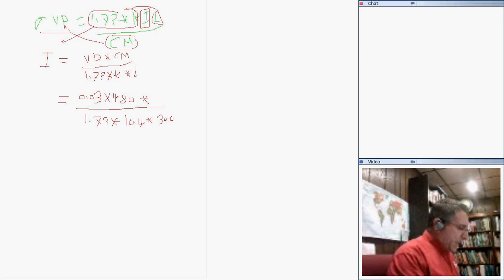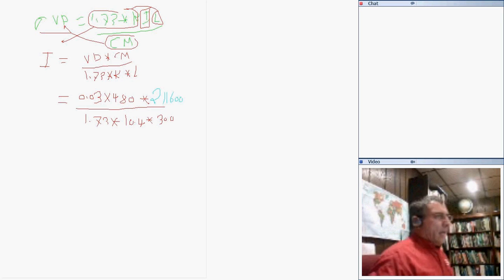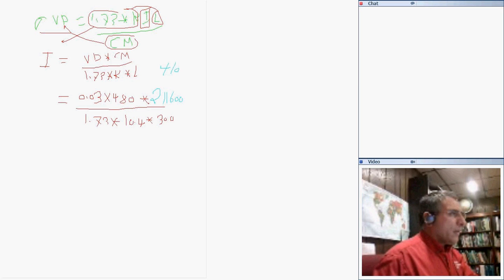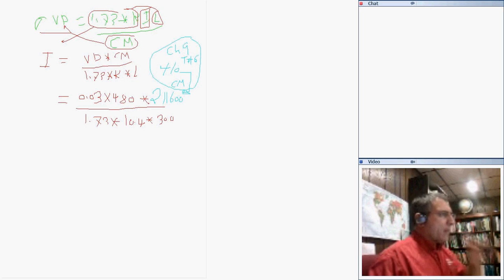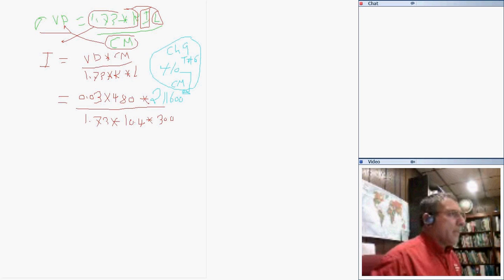So I'm going to go to Chapter 9, Table 8. You're going to find the circular mil as 211,600. Everybody got the 211,600, circular mils? This is the circular mil for 4/0. Remember that. Let's have a note: Chapter 9, Table number 8, not number 6. The circular mil for 4/0 is 211,600.